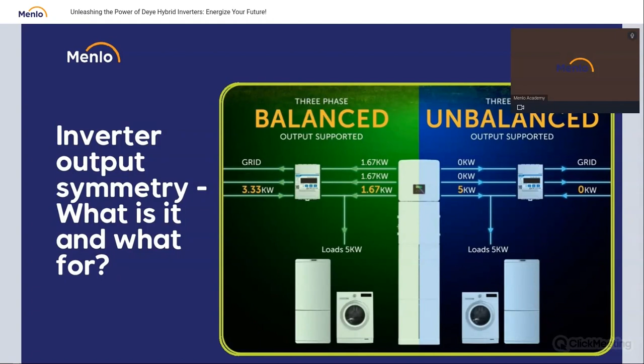And the last, not last, one more thing which I want to tell you about, it's backup limitations. In an on-grid situation, there is no problem. If our installation doesn't produce enough energy, we buy it from the grid, we don't have to worry about anything. But there are situations when our installation switches into backup mode, when the grid is off, or something happened with the grid, so there is some maintenance work, something like that. Then we have three backup limitations, which cause that our system might collapse, might turn off.